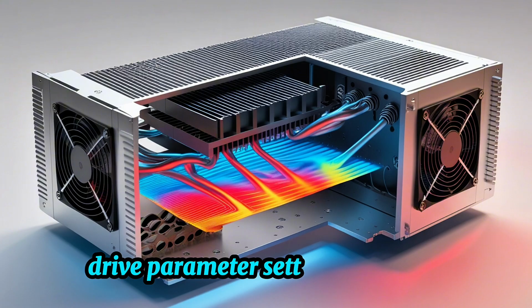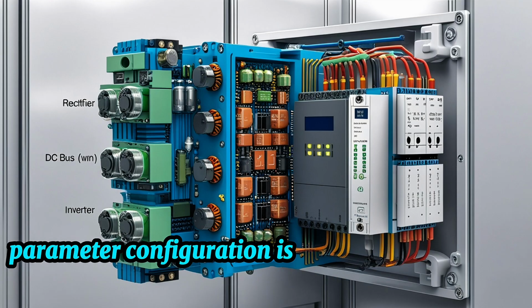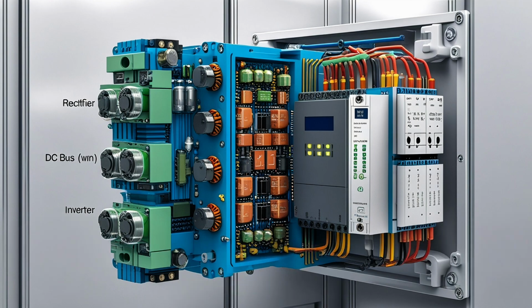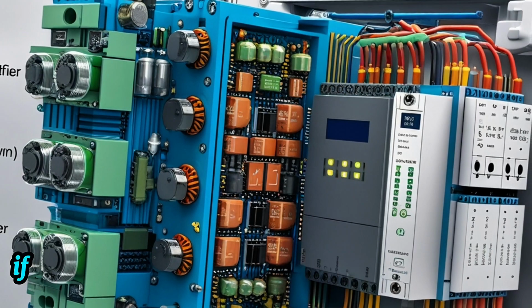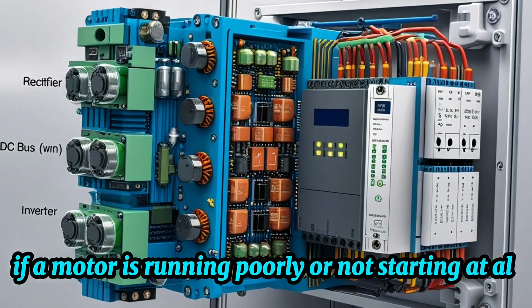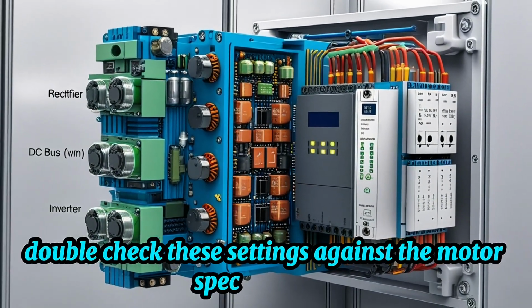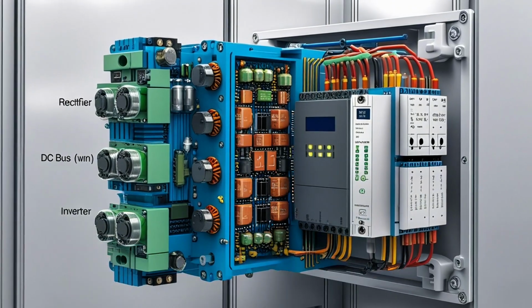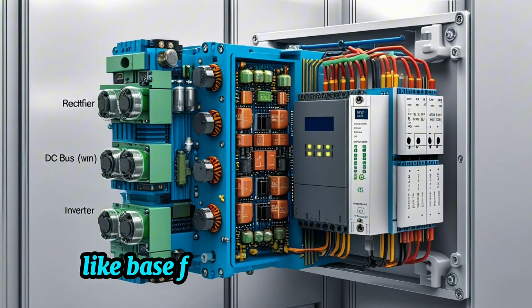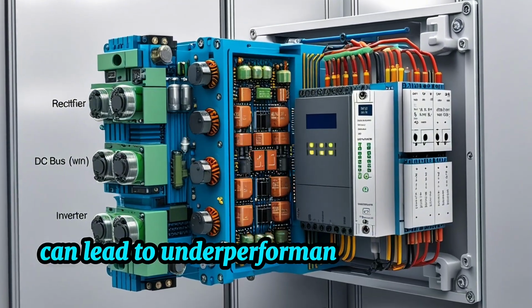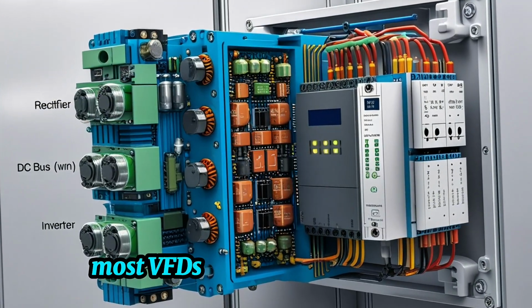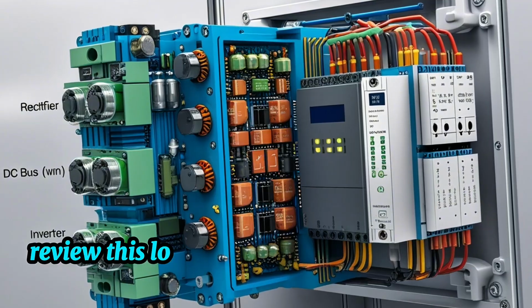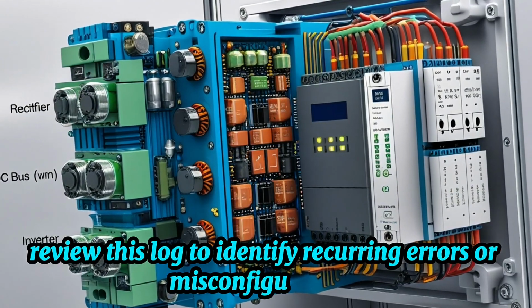Drive parameter settings. Incorrect parameter configuration is a common and often overlooked issue. Parameters control critical aspects like acceleration and deceleration rates, maximum frequency, voltage limits, motor nameplate data, and protection features. If a motor is running poorly or not starting at all, double-check these settings against the motor specifications and the application requirements. Even a small mismatch in a parameter like base frequency or current limit can lead to underperformance or nuisance tripping. Most VFDs also store fault history. Review this log to identify recurring errors or misconfigurations.